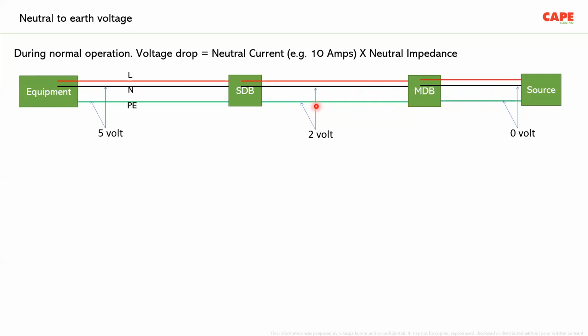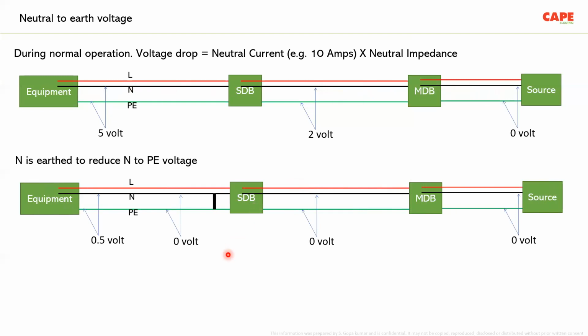A little bit away from the source, the voltage is probably 2 volt, because there is a small voltage between neutral and earth. Nearer to the equipment, the voltage is probably about 5 volt. And this 5 volt, where does it come from? It comes from the voltage drop in the neutral conductor. Technically, this voltage has nothing to do with earthing. This is the voltage drop in the neutral conductor.